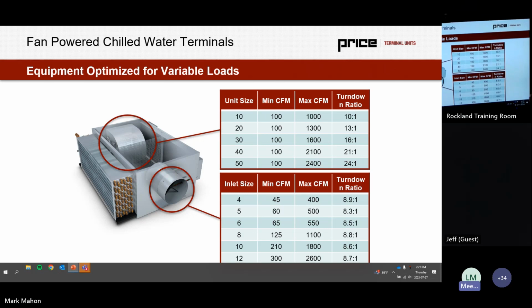For the primary air damper, an 8.5 to 1 turn down ratio is my rule of thumb because that covers all of them. And that 8.5 to 1 turn down ratio is also large. I would generally recommend, I like a 4 to 1 turn down ratio as a maximum rule of thumb for a VAV damper inlet. And usually that's 2,000 feet per minute down to 500 feet per minute as a pretty solid design rule of thumb.